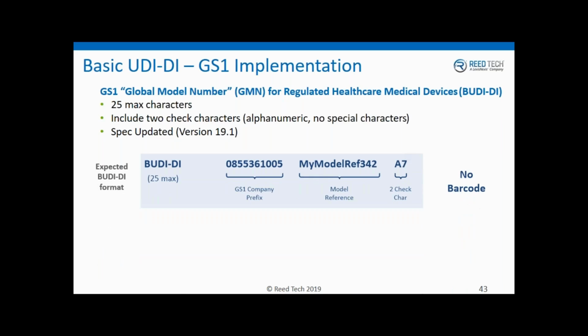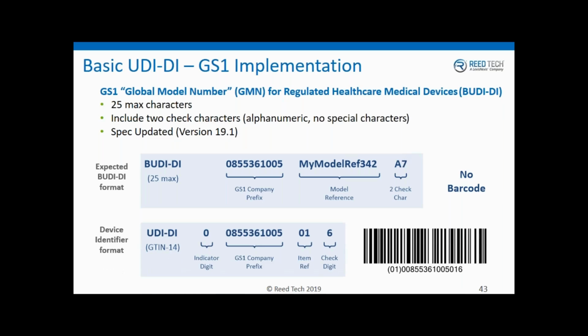And their definition has 3 components that go into a BUDI: a company prefix, a model reference number, and again, noteworthy, this is able to be alphanumeric. So normally a GTIN would only have numbers in it, but this can be alphanumeric, and these 2 together can be up to 23 characters. Doesn't have to be that, but the max is 23 characters. And then GS1 built a specification algorithm on how to create the 2 check characters. And again, there's no barcode associated with that.